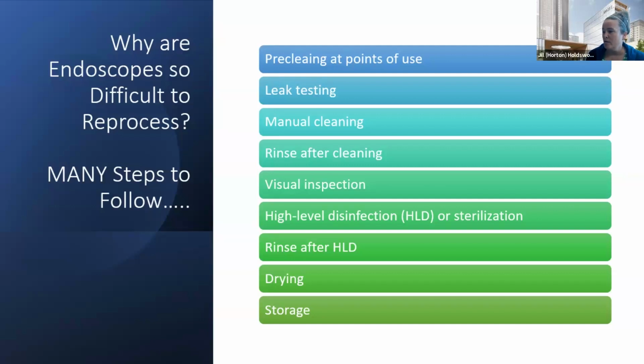After that, we either do our high-level disinfection or sterilization. Again, a lot of steps happening there. We rinse, we dry. Sometimes we dry in our HLD machine. Sometimes we dry outside, and I'm going to talk about some failures with drying. And then we have to store them. We have to store them correctly in cabinets that actually are compliant. And then we have to make sure we're keeping track of how long we store them. We can't just store them for years and then pull them off the shelf and reuse them. So there's a lot of steps to follow.